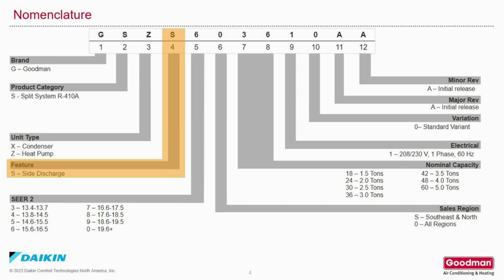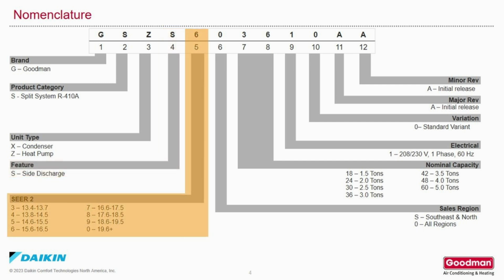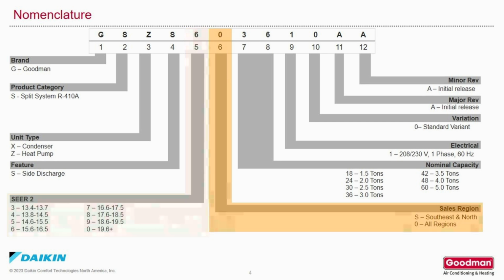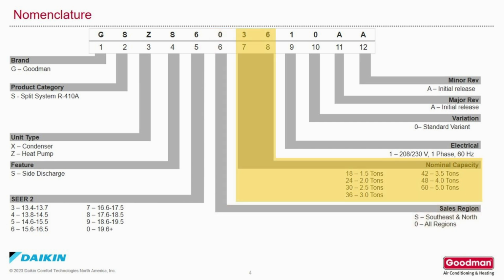The next position is for the feature. S stands for side discharge. The next position is for the SEER rating. It ranges from 13.4 to 19.6. The next position shows the sales region. S for Southeast and North, 0 for all regions. The next two positions, position 7 and 8, are for the nominal capacity of the outdoor unit, 18,000 BTU, 1.5 tons, through 60,000 BTU, 5-ton capacity.